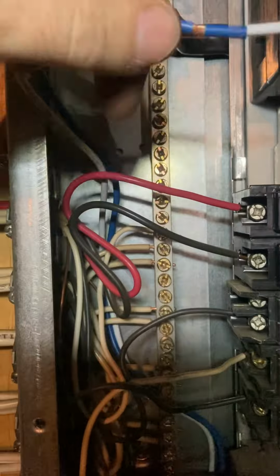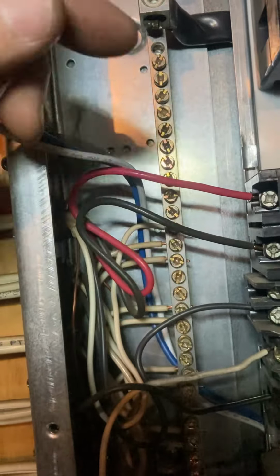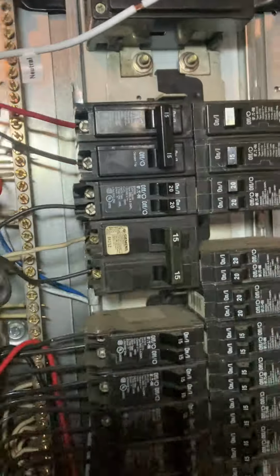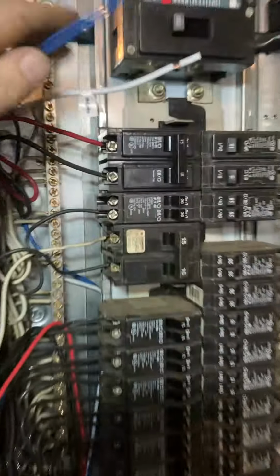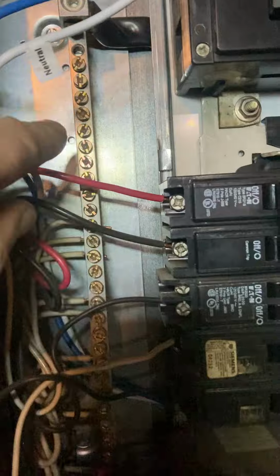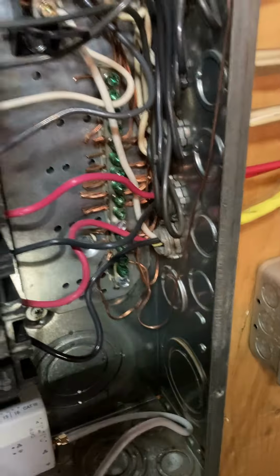So I've got these two that are going to go into the neutral. On a 200 amp split phase panel like this, these two are going to go to the neutral bus bar, which is this guy, not to be confused with the ground, which is over here.